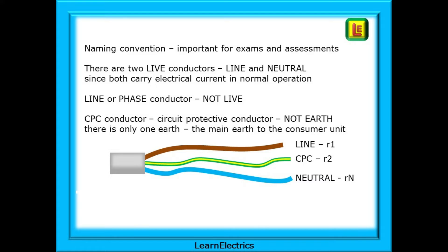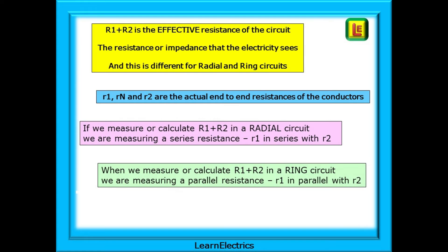Why little and not big? Big R1 plus R2 is the effective resistance of the circuit and may not be the actual resistance of the conductors. It is the resistance or impedance that the electricity sees, and this is different for radial and ring circuits. How they are connected makes a big difference to the effective resistance. But little r1, little r2, etc. are the actual end-to-end resistances of each conductor and they are unchanging.